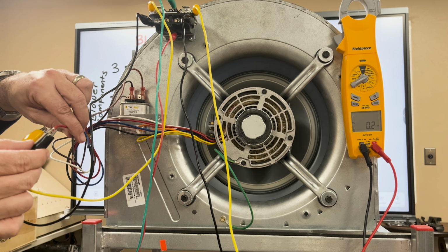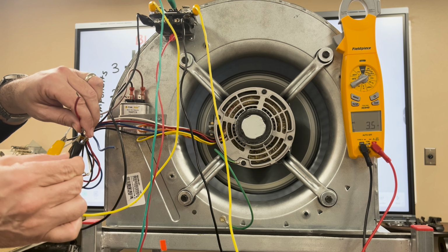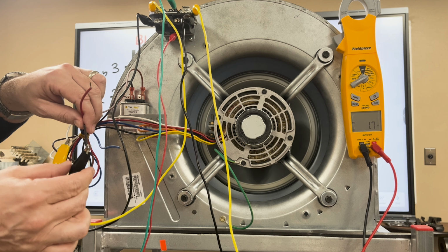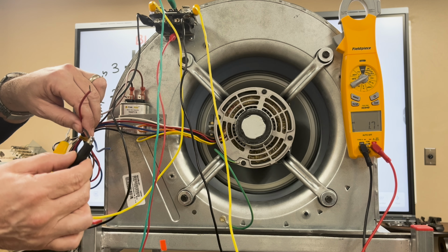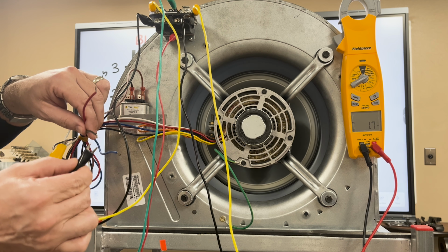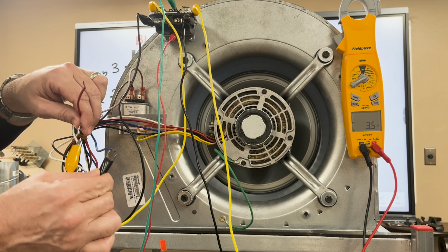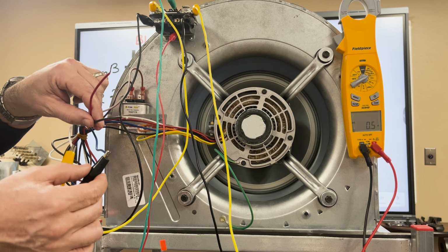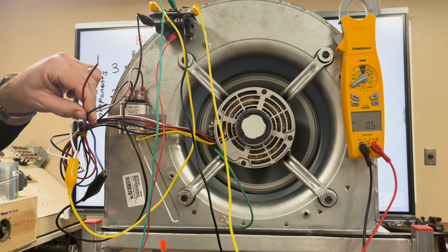So we have low speed, we have medium speed, and then beyond that, we have high speed. Now you might be asking, what speed do we normally use? Well, the manufacturers recommend medium speed for cooling, which gives you roughly 400 CFMs of air per ton. Then they recommend either medium speed or low speed depending on what type of heating you're running.